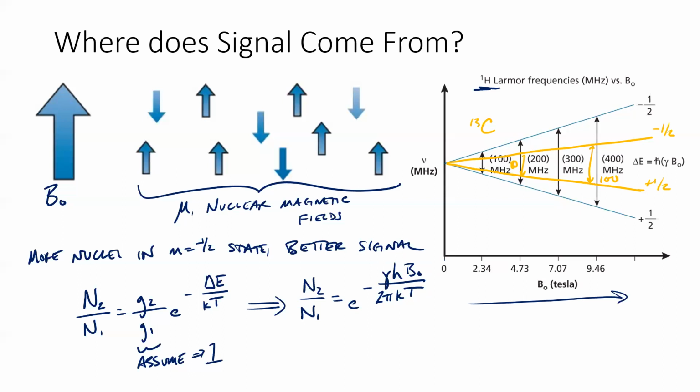They have to be super cooled, and so they're cooled with liquid helium. The liquid helium is actually kept cold by a jacket of liquid nitrogen, so your helium doesn't go away too quickly. And so the inside of this magnet is pretty chilly. So we're at relatively low temperatures as sort of a side effect of being at very high field strength. So that's a cool thing about it.